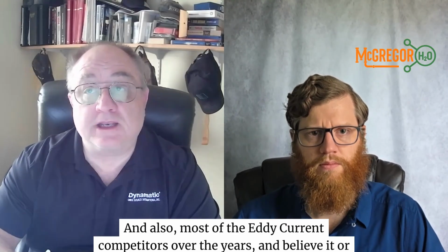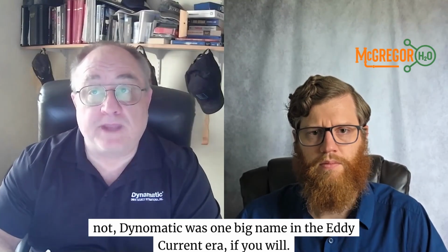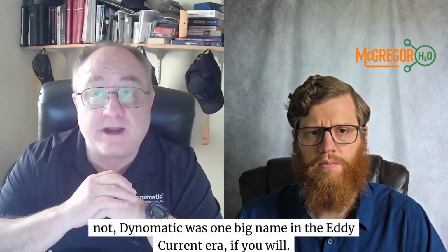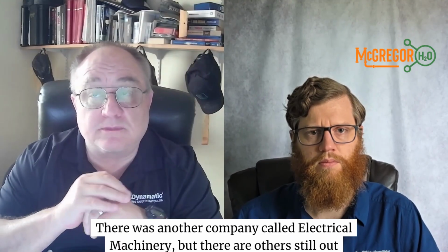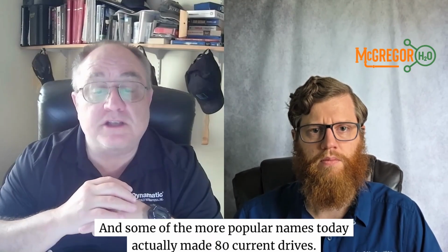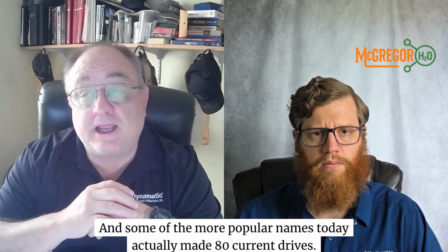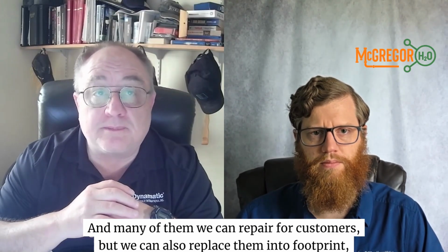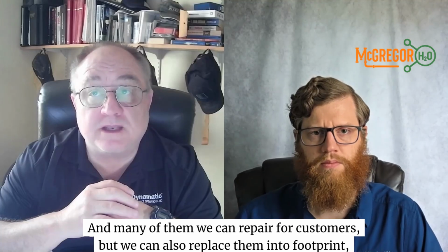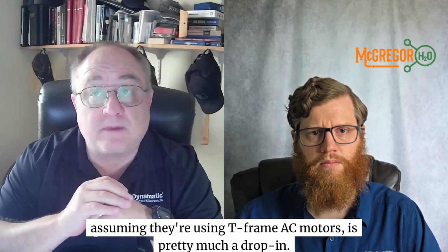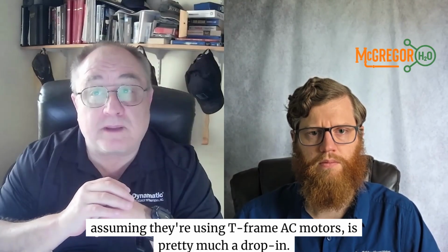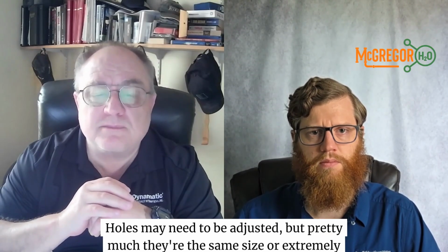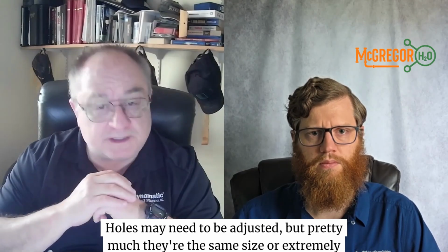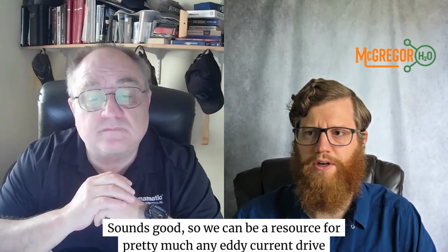And also, most of the eddy current competitors over the years, and believe it or not, Dynamatic was one big name in the eddy current era, if you will. There was another company called Electrical Machinery, but there are others still out there, even Hyundai and Toshiba and Yaskawa, and some of the more popular names today actually made eddy current drives. And many of them we can repair for customers, but we can also replace them, and the footprint, assuming they're using T-frame AC motors, is pretty much a drop-in. Holes may need to be adjusted, but pretty much they're the same size or extremely similar. Sounds good. So we can be a resource for pretty much any eddy current drive application.